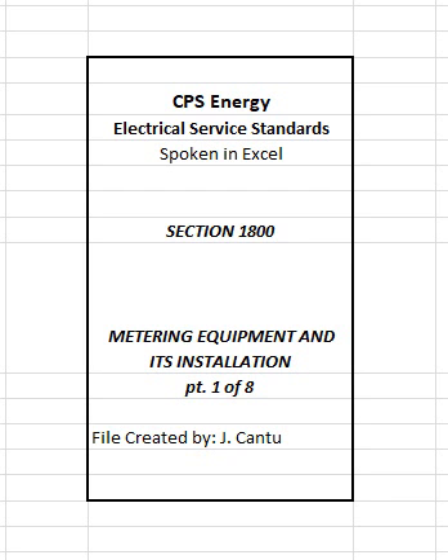Note: customer shall be responsible for furnishing and installing residential single-phase, self-contained meter sockets. CPS Energy does not furnish this metering equipment. The general installation requirements outlined herein for self-contained meter sockets shall be applicable.